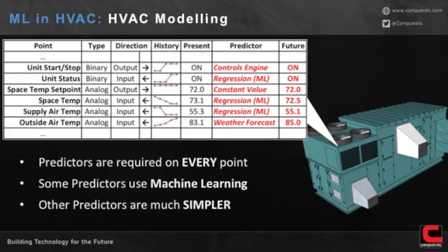So let's look at a couple of examples. Here we just took a small collection of points related to a single piece of equipment. We've got the unit start-stop, the thing that actually drives it. Unit status, that's the feedback, typically taken off a current transducer or something. Space temp set point, what do we want the temperature to be? The actual space temperature, supply air. And you'll notice some are ins and some are outs—we only need machine learning on the inputs.